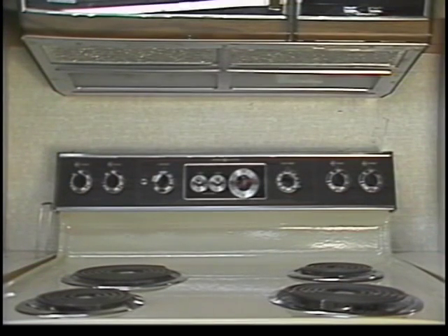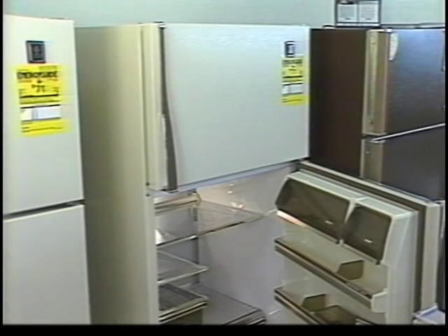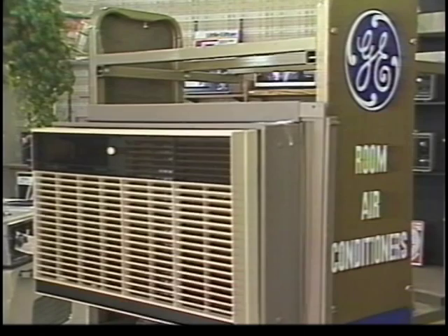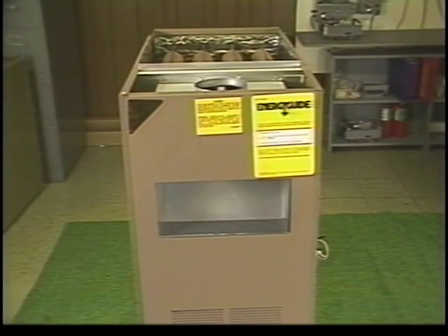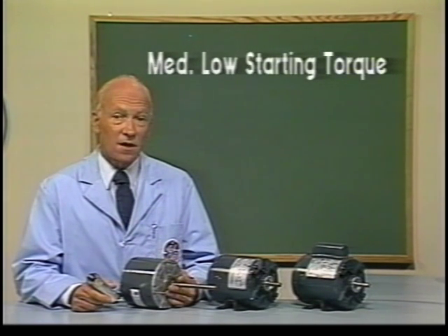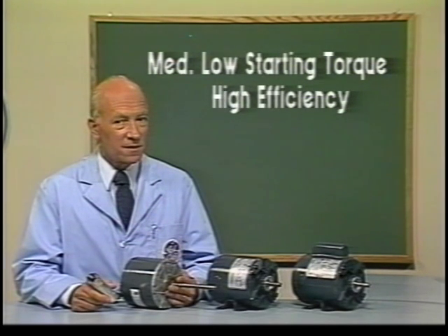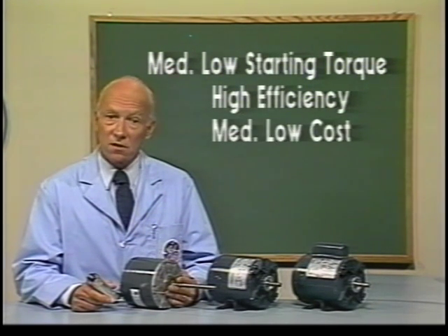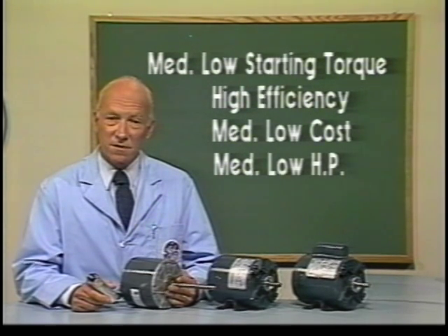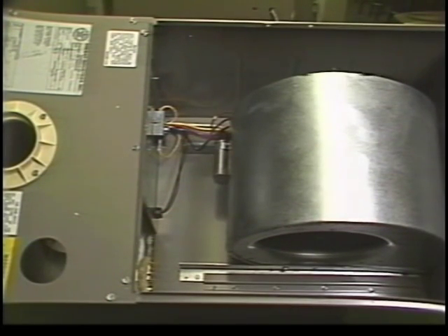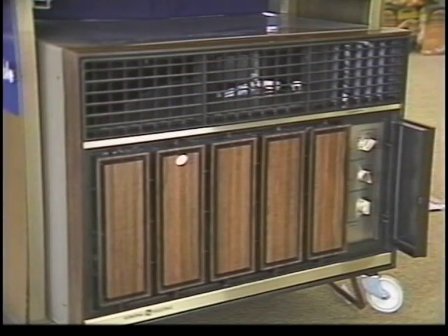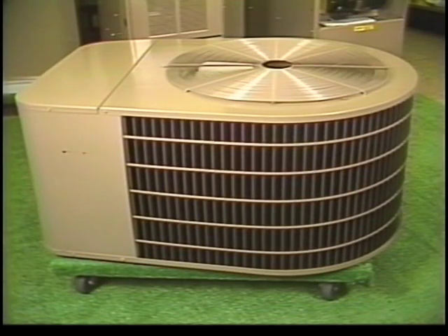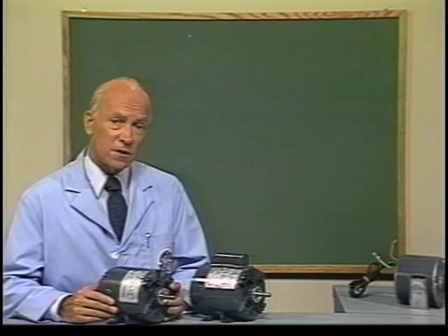The shaded pole motor has low starting torque, low efficiency, low cost, and a low range of horsepower. It is most often found in small vent fan applications and with the small fans found in refrigerators, room air conditioners, and furnaces. The permanent split capacitor motor has medium-low starting torque and the highest efficiency of the four types. The PSC also has medium-low cost and horsepower range.